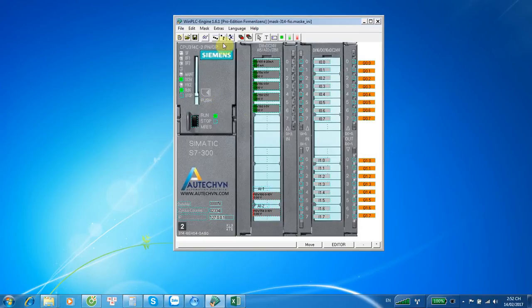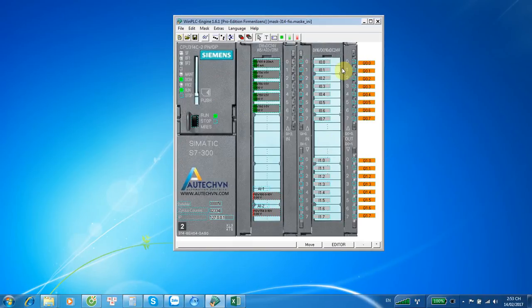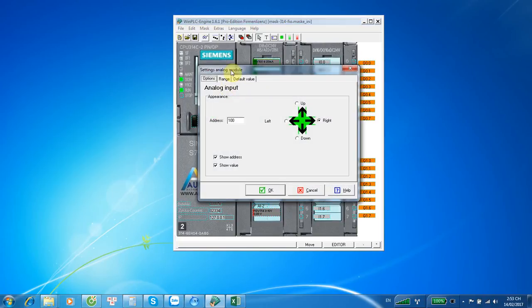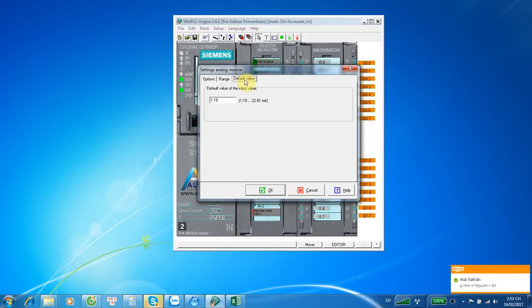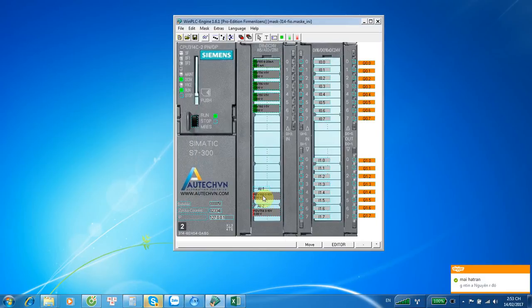On this interface, we can see the left side shows the status of the PLC, like CPU run or stop status. This is the indicator for the status of input and this is the indicator for the status of output. Here we can see the analog input nodes and the analog output. We can configure the address of the analog input, the range of the analog input, the default value of the analog input, and same for the analog output.